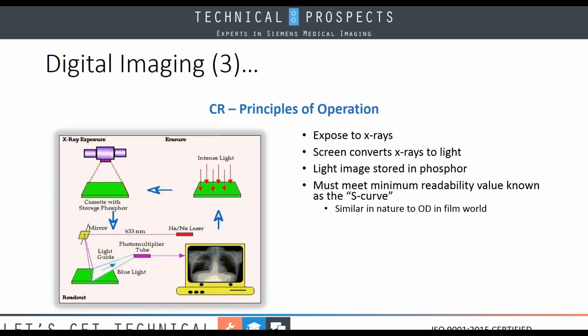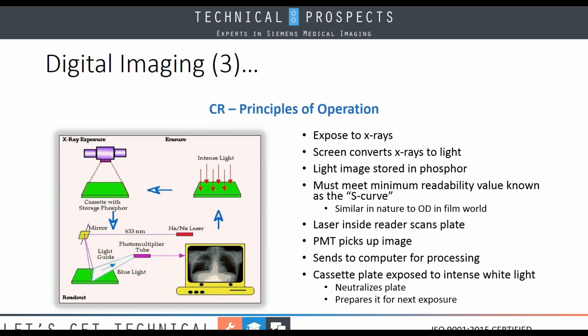Once we've achieved that minimum value, we have the laser that goes inside through the mirror and scans our storage phosphor. All right. This excited storage phosphor now is being read by the photomultiplier tube, which takes this and sends it to the computer for processing, and our computer program then is what compiles our image. While that is going on, in order to reuse the cassette, we're going to send the cassette and we're going to expose it to intense white light, which basically neutralizes the plate and prepares it for the next exposure. And that will then allow us to reuse the cassette moving on.